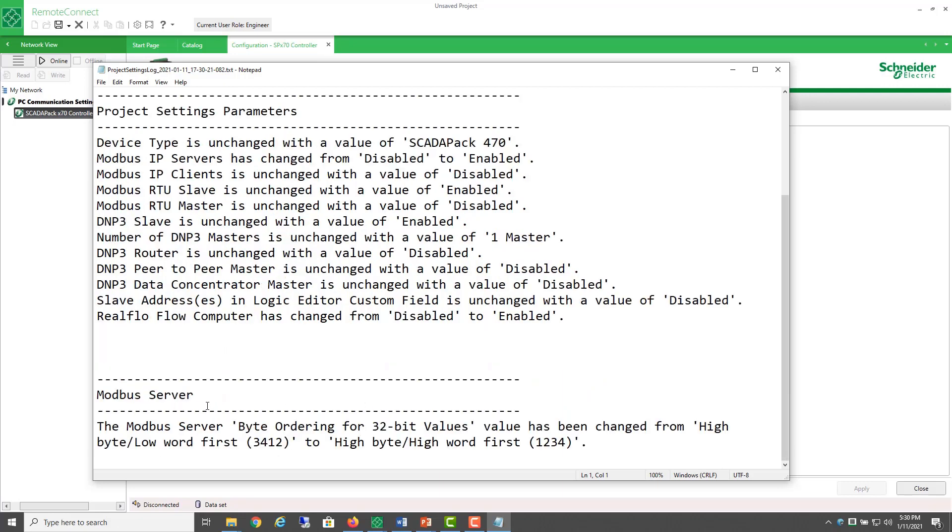In the Modbus server, this is both Modbus RTU and Modbus TCP, the order for 32-bit values has been changed from the default of 3412 to this order, 1234.